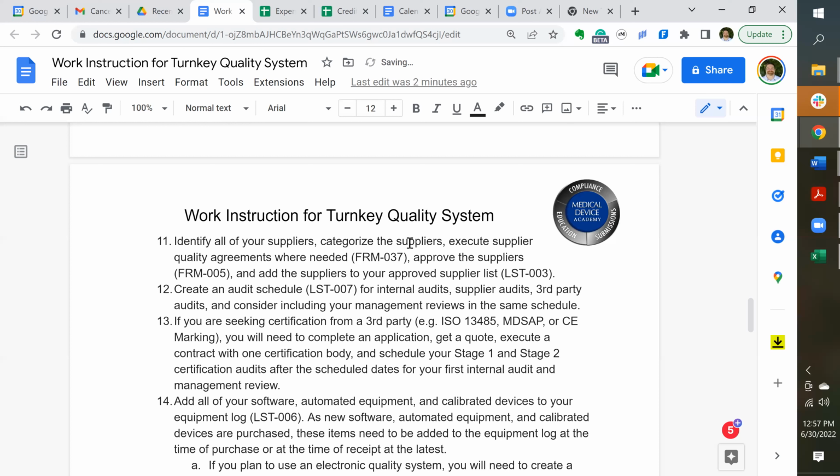The next one down the list, they don't need to be audited, but you should have some sort of agreement in place that says they'll notify you of a change. It could be in your purchase order. The other two, the crucial and the critical, you probably need a supplier quality agreement. And then the consultants, a resume, scope of work agreement, confidentiality, training certificate for lead auditor. Those are the appropriate things for that group. Do not use the supplier questionnaire that you have for crucial and critical suppliers for your consultants because it just pisses them off.